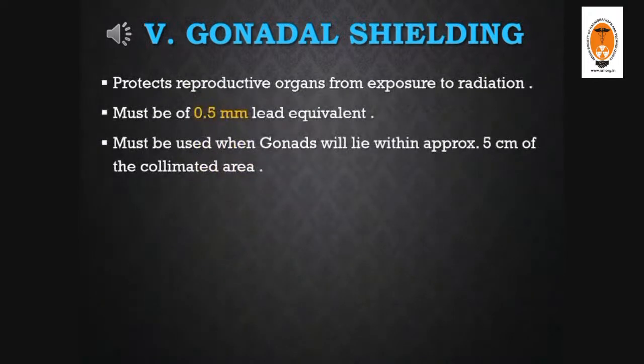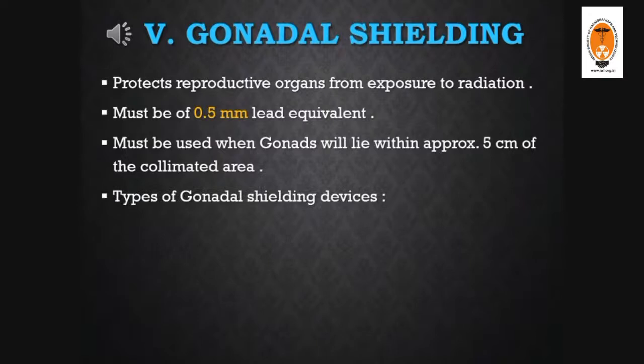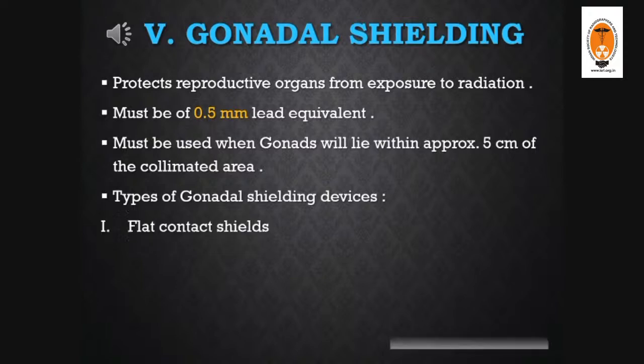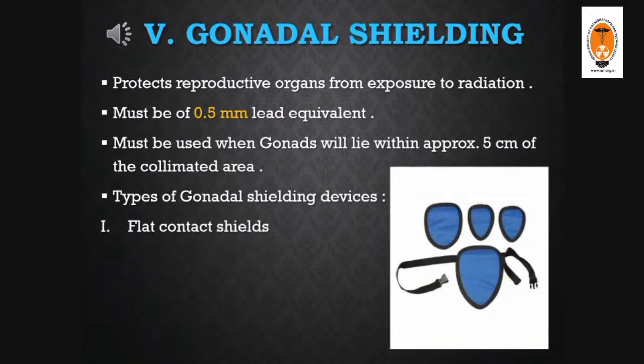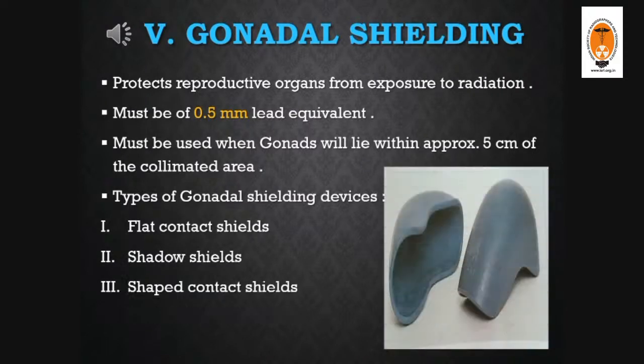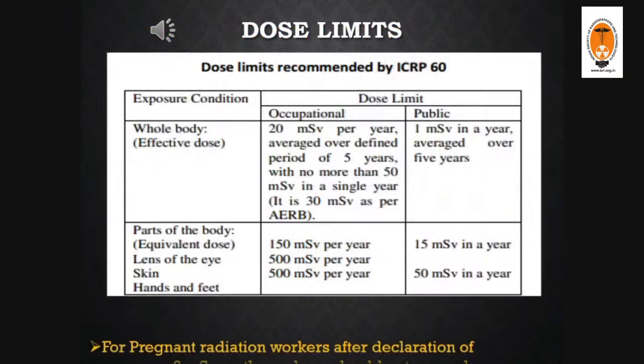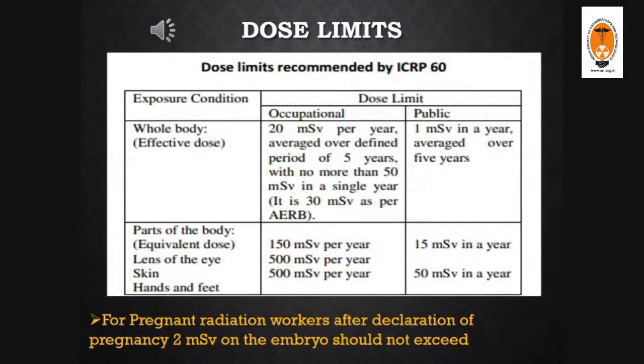Next are gonadal shields. These protect the reproductive organs from exposure to radiation in males and females, and these have about 0.5 mm lead equivalence. They are of different types, like flat contact shields, shadow shields, shaped contact shields, or clear lead shields. Here is a chart showing the dose limit recommended by the ICRP for an occupational worker as well as the public, that is, a patient, for the different parts of the body.